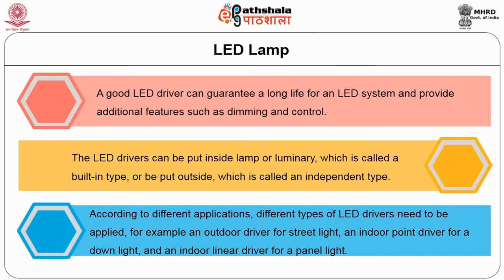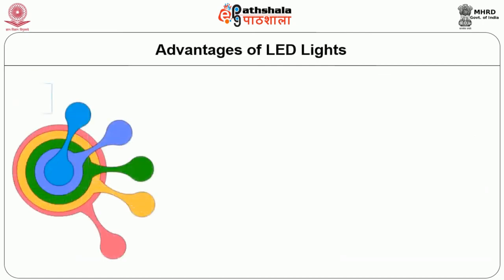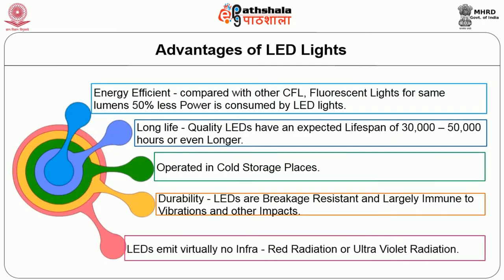Advantages of LED light: energy efficiency compared with CFL and fluorescent lamps — for the same lumens, LED lights consume 50% of the power. Long life quality: LEDs have an expected lifespan of 30,000 to 50,000 hours or even longer. They can operate in cold storage places. Durability: LEDs are highly durable, breakage resistant, and largely immune to vibrations and other impacts. LEDs emit virtually no infrared radiation or ultraviolet radiation.